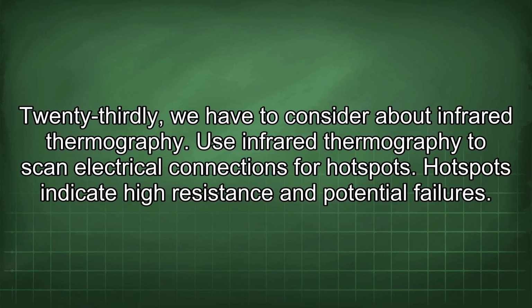23rdly, we have to consider infrared thermography. Use infrared thermography to scan electrical connections for hotspots. Hotspots indicate high resistance and potential failures.